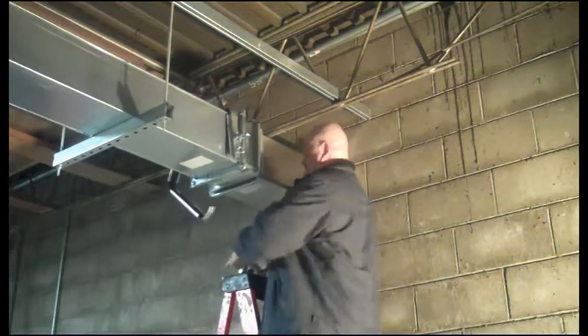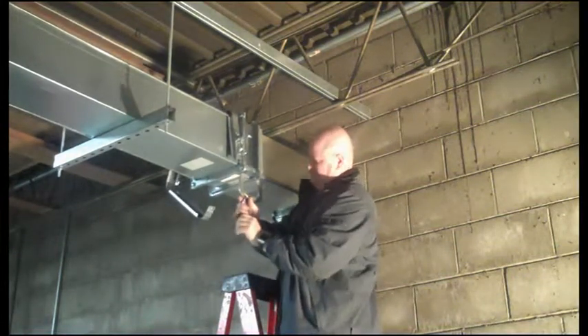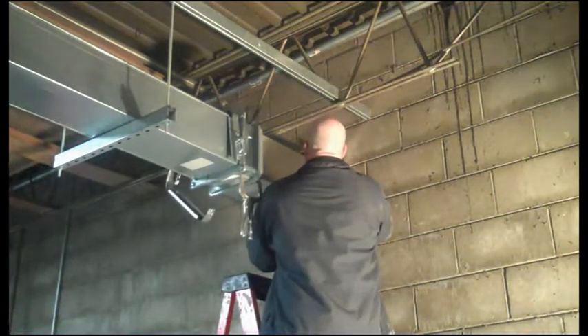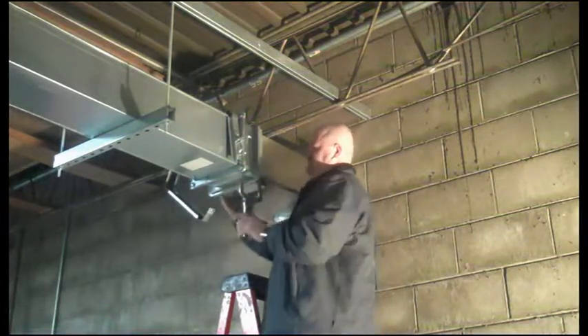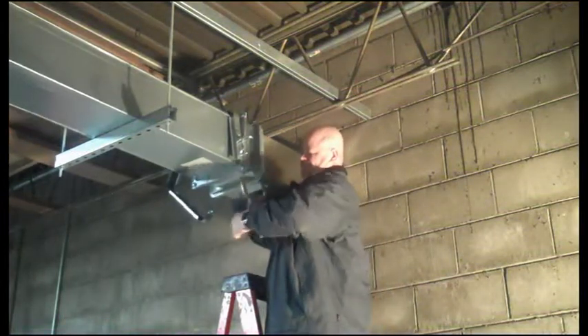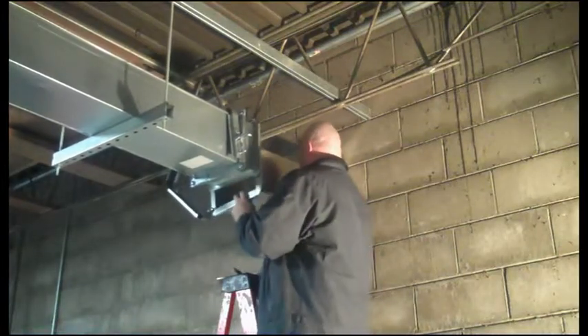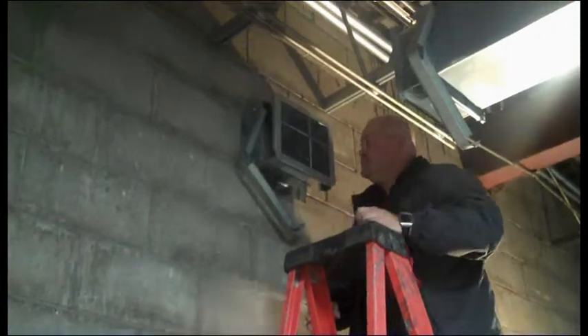As a building owner, the new fire and smoke damper inspection requirements create further challenges for existing duct construction methods — more specifically, proper access to these dampers. It is next to impossible to properly maintain your fire and smoke dampers unless you have adequate access to them. NFPA 80 section 19.2.3 on access states that dampers equipped with fusible links, internal operators, or both shall be provided with an access door.